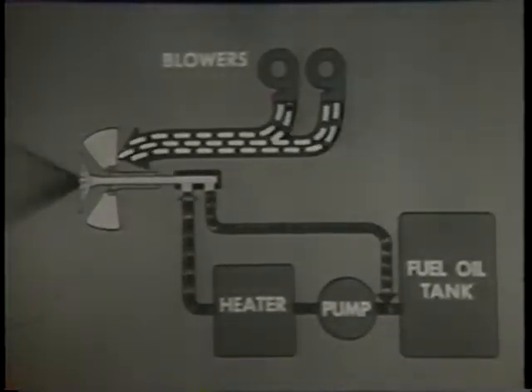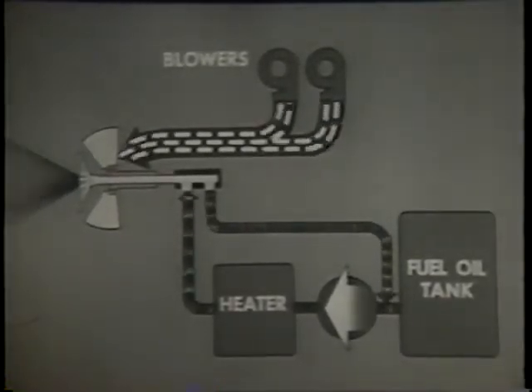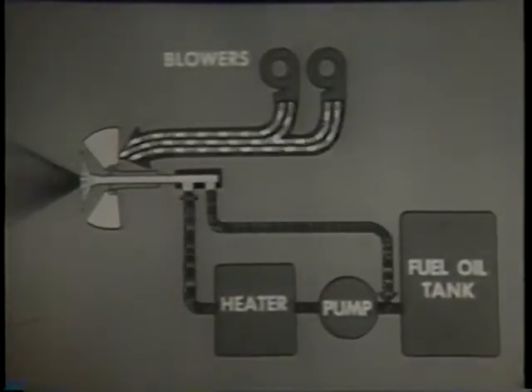At the burner's maximum firing rate, practically all the oil enters the furnace. At the minimum firing rate, practically all the oil returns to the pump. In controlling the fuel supply to the burner, you keep the pressure on the oil entering the burner constant and at the maximum for the system. You vary the pressure on the return line. When you close down on the return line valve, less oil can get through; as a result, the pressure builds up in the return line. This greater pressure forces more oil into the furnace than before. When you open up on the valve, the valve passes more oil and return line pressure drops, so less oil enters the furnace. Varying the speed and number of the force draft blowers is the principal method of controlling the burner air supply. You can make limited adjustments to the air supply with the air doors.